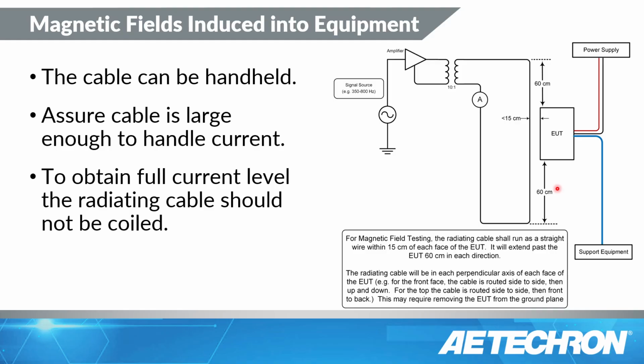Since you also have to do it over a number of frequencies, it might be easier to have the wire in one location, 15 centimeters apart from the unit, and run through the frequency scan and then move it over a bit. So maybe 2 or 3 positions across the top face or 2 or 3 on the side, and you'll get through it fairly quickly. There's not a lot of frequencies that you'll have to test.